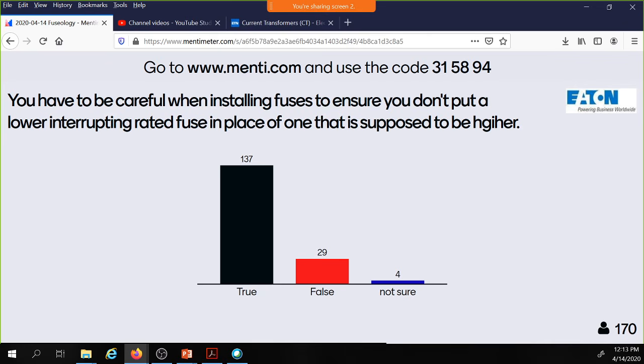So the good thing about fuses as well is they have rejection features, so that you can reject on voltage, you can reject on current limiting and interrupting ratings. So that's a very nice feature of fuses. It helps, even in the installations, makes it easier and a little bit more foolproof, because they do have the ability to reject, which makes it a lot more difficult to screw up the installation in the field. So that's another nice thing of these fuses. I would say that false is actually the right answer here, because I have the rejection features on fuses that help prevent a mistake in the field. I don't necessarily have that on circuit breakers, but I do have that on fuses.